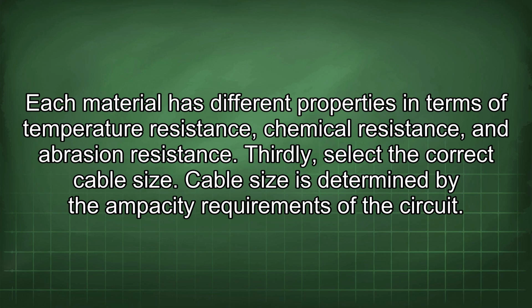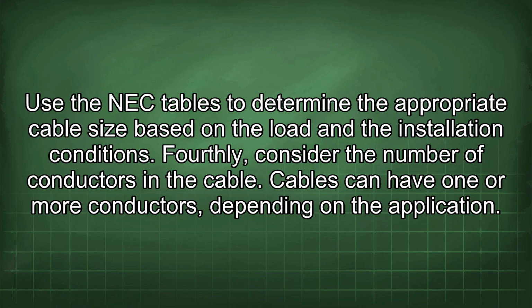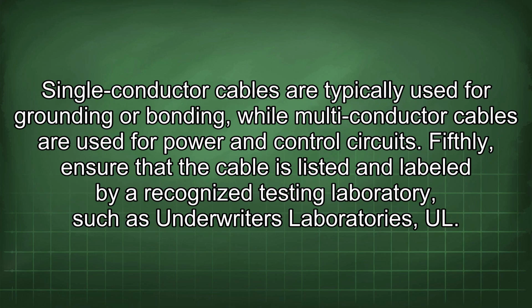Thirdly, select the correct cable size. Cable size is determined by the ampacity requirements of the circuit. Use the NEC tables to determine the appropriate cable size based on the load and the installation conditions. Fourthly, consider the number of conductors in the cable. Cables can have one or more conductors depending on the application. Single conductor cables are typically used for grounding or bonding, while multi-conductor cables are used for power and control circuits.